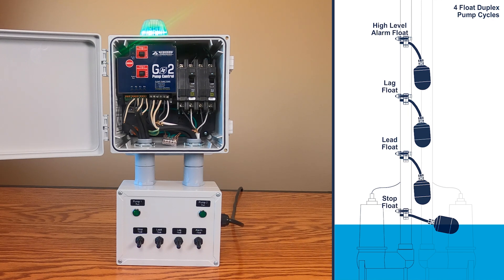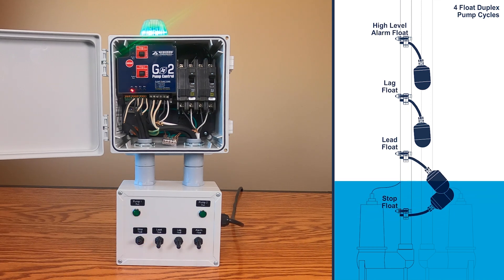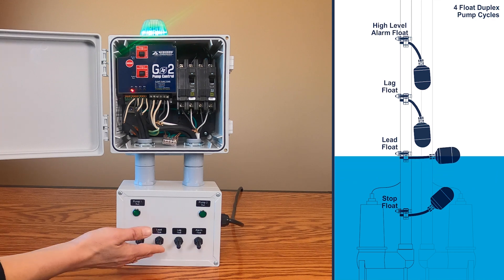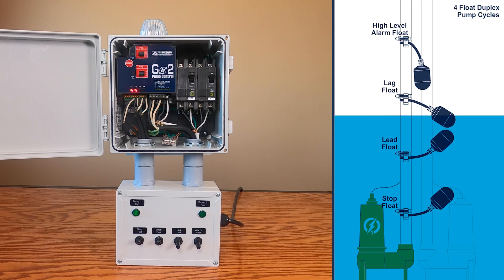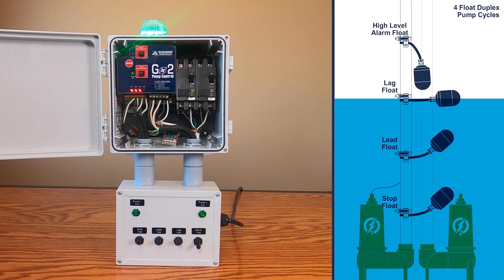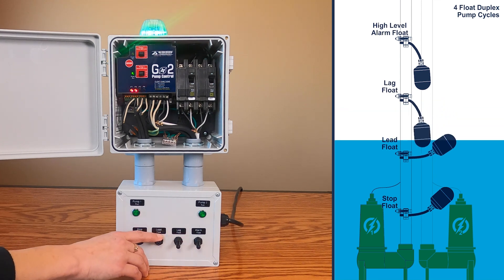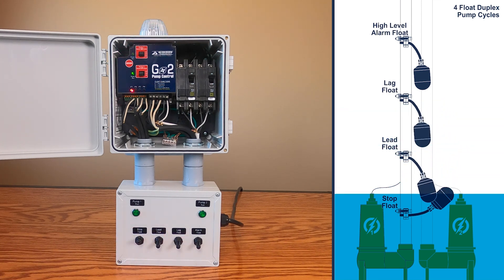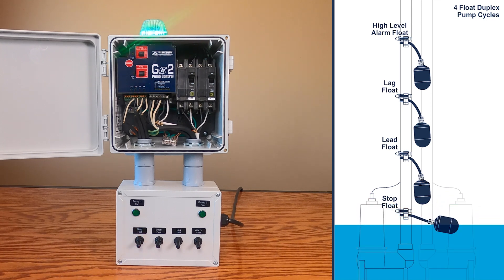Next, let's simulate a lag pumping cycle. As the water rises, the off float will activate. The water level continues to rise and the lead float will activate and pump 1 will turn on. The water level continues to rise and the lag float will activate and pump 2 will turn on. As the pumps are lowering the water level, the lag float will tilt down, then the lead float, but the pumps will remain on all the way down to the off float. This completes the lag pump cycle.